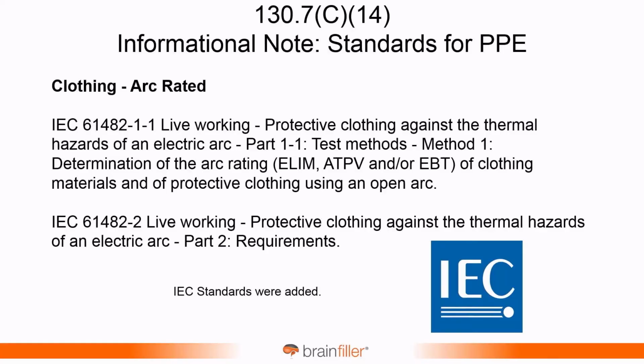One of the things that happened during this, I'm an ASTM member, although I'm not as active as I should be, was that at the top level of this ASTM committee, they sent out an email. There was a lot of heartburn over moving it out, and a statement was made about how next thing you know, we're going to be using IEC standards. And well, being chairman of all those standards, I had to put on my official IEC hat and fire back. It's like, wait a minute. IEC standards are just as good and maybe even a little more stringent than ASTM standards. But what happened along the way is, guess what? In 2021, the IEC standards have made their way into this.